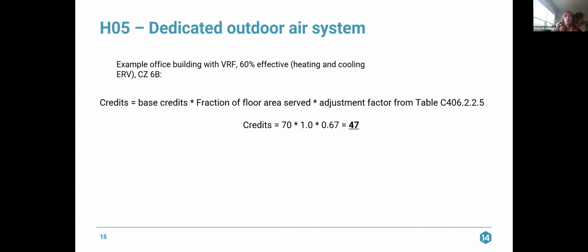So here's our example. We have an office building with VRF. Our energy recovery ratio is only 60%, and we're in climate zone 6B. We're going to take the base credits, which is 70. I'm saying that the entire building is served by this system, so we multiply by the fraction of floor area served, which is 1.0, and we're only at 60% effectiveness, so we're at 0.67. So 70 times 1 times 0.67 gets us 47 credits.